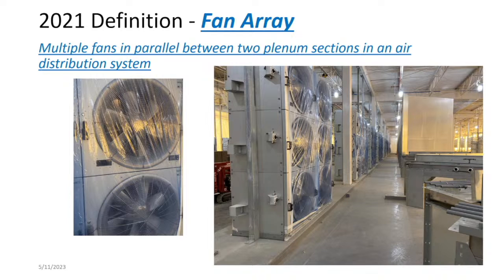And you can see down there, I was halfway down, so there's a little hallway between, so it's not 1,200 feet long altogether. It's about 600 feet with a separation in it. So you can see over here, this is under construction. This is where they're going to pull in fresh air. There's a big filter rack that goes there. And then these fans suck in air from outside. And then here they are building their evap cooler sections. In between they had dampers so you could do some bypassing and pressure control and such.